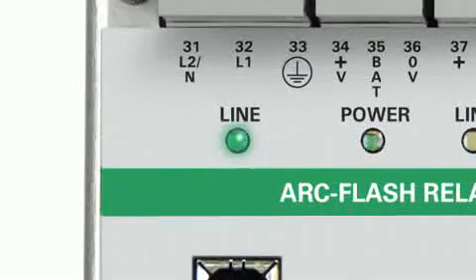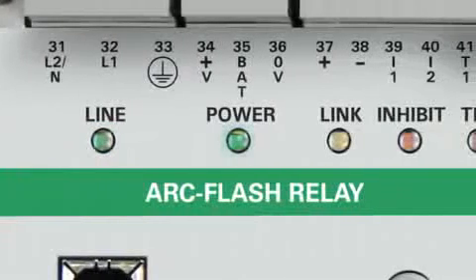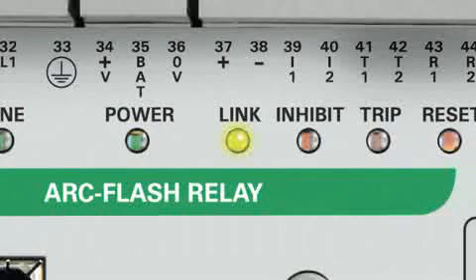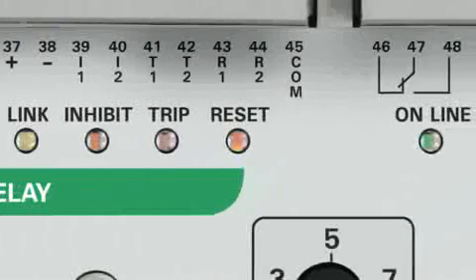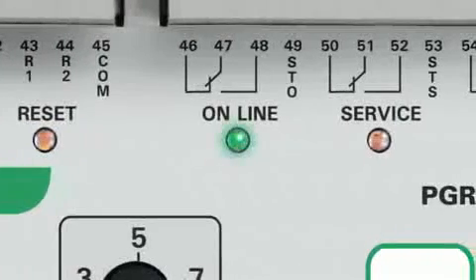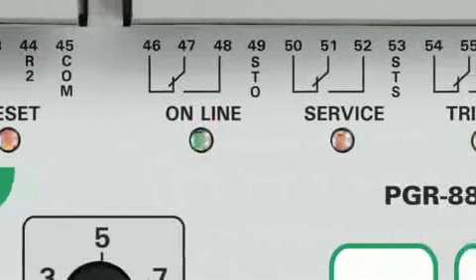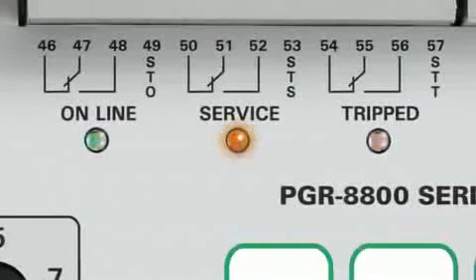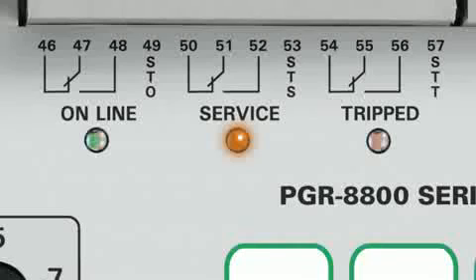Line voltage: if you were to bring it in with control powered AC, you would have a light here. Power: we're powering the unit with DC. Our link says that we have 2 units linked together to tie into one shunt trip breaker. Our reset is for the remote reset. Online lets you know that your relay is online. We have 2 types of service modes. One is for an initial setup. The second will engage the trip coil.